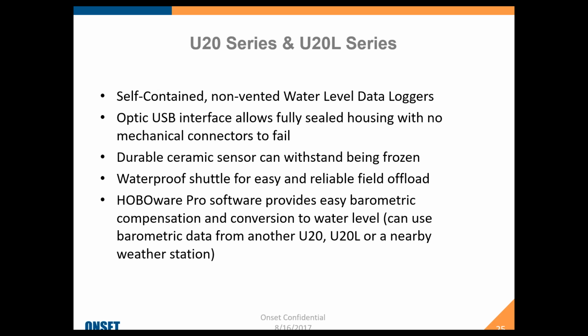HOBOware Pro has a nice, easy barometric data assistant to help you perform that. You typically put in your reference reading, the kind of water you're in, whether fresh, salt, or brackish, and your barometric pressure reading, and the software does the compensation. So your data file gives you pressure, temperature, and water level to the hundredths of a foot.